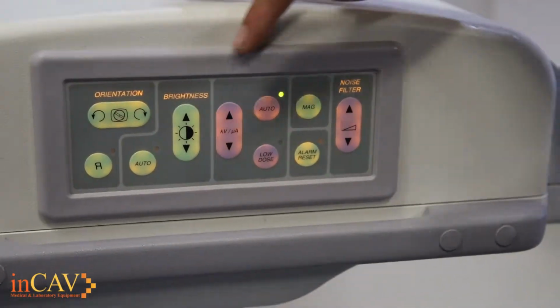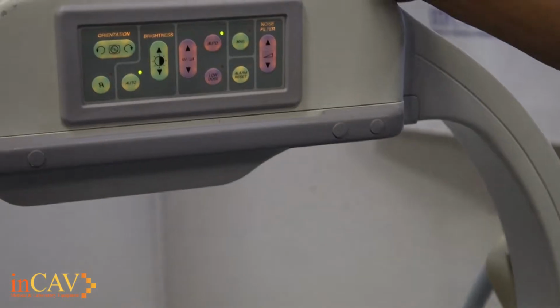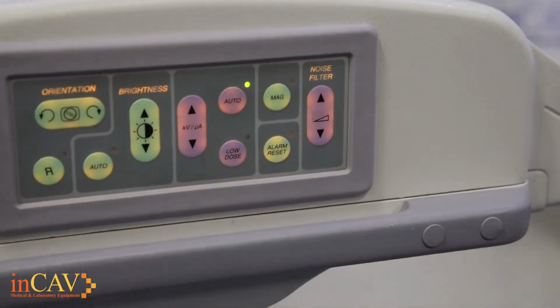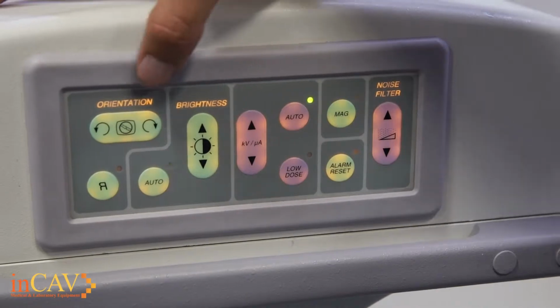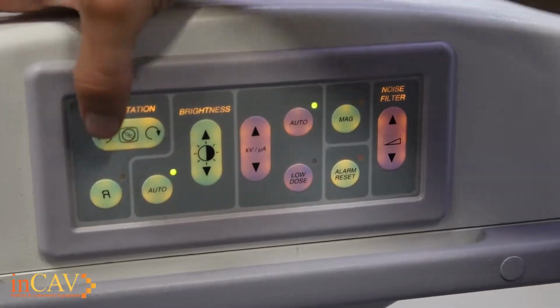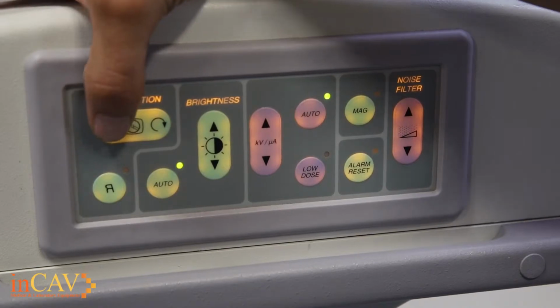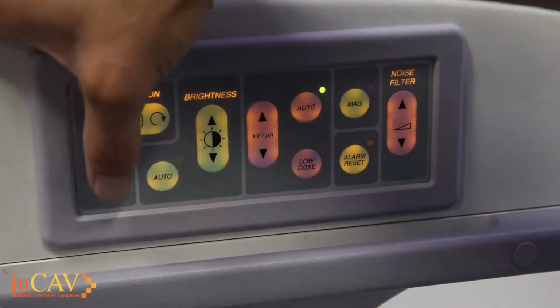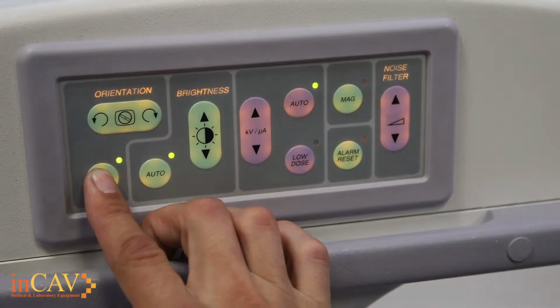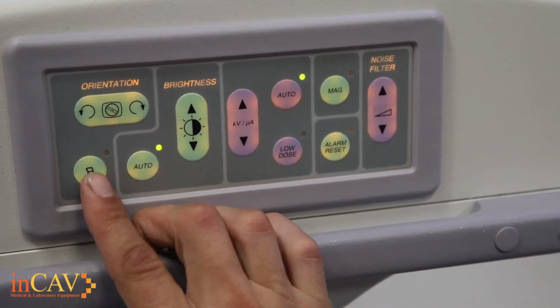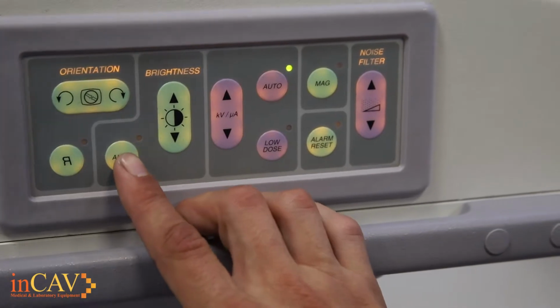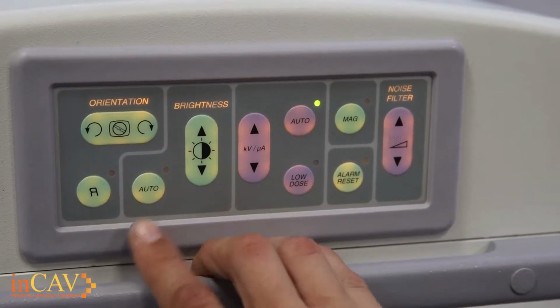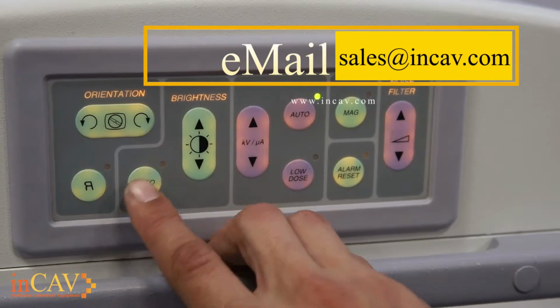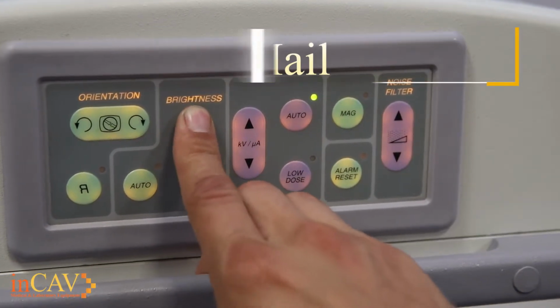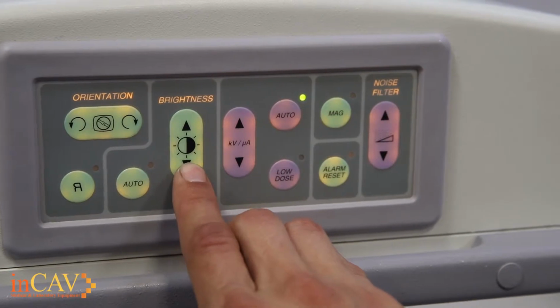This is the control panel located on the C-arm itself. This is going to be different from what's on the workstation. This is your collimator adjustments here. This is going to change your orientation. You'll actually be able to hear it when you make an adjustment. This right here will actually flip the image on the screen itself. Now this right here is also going to affect your brightness. Automatic, if you want to set it for automatic, or you can adjust it manually here, and that'll change the brightness and contrast on the actual screen itself.